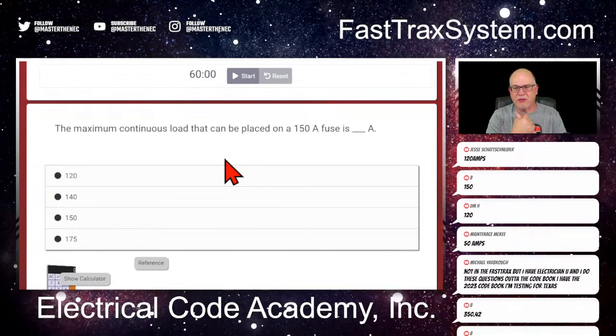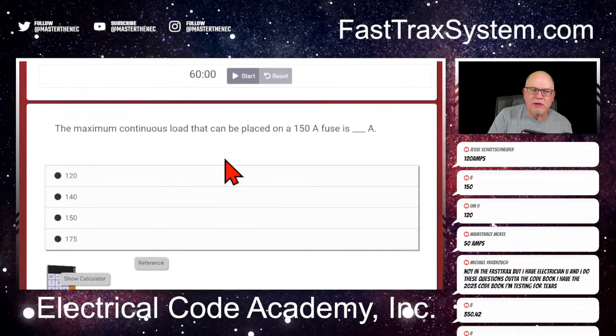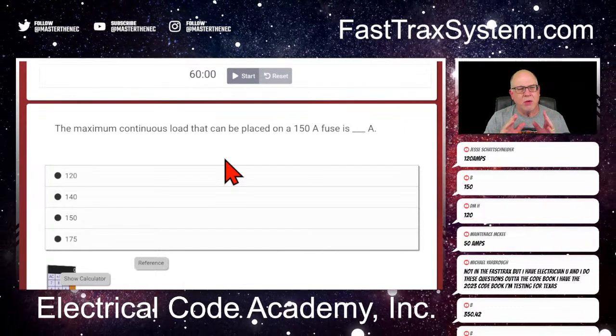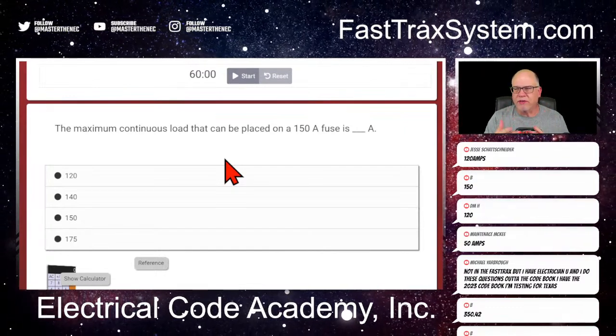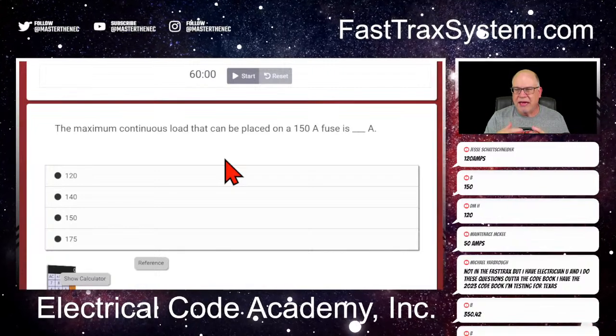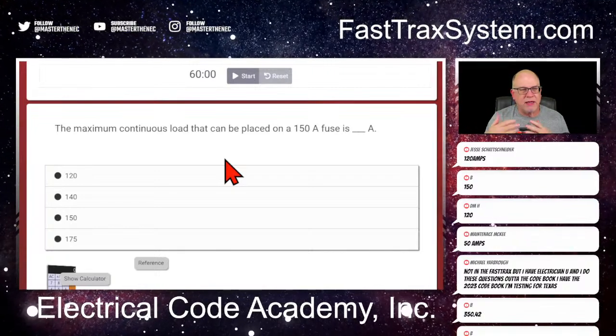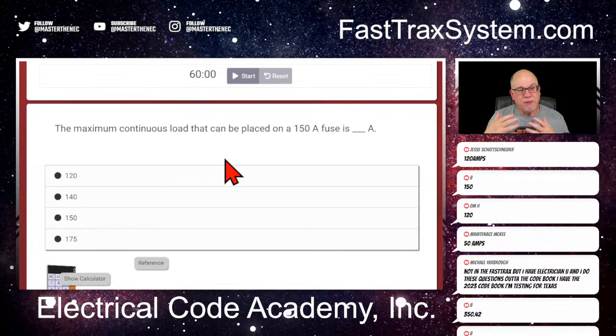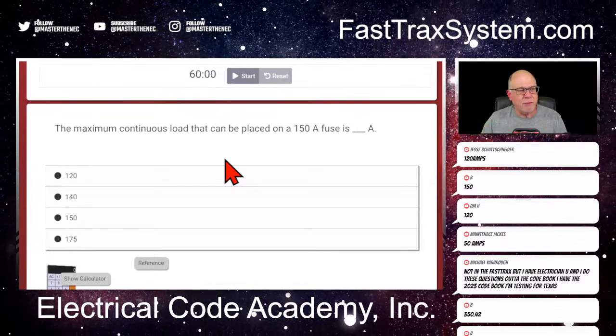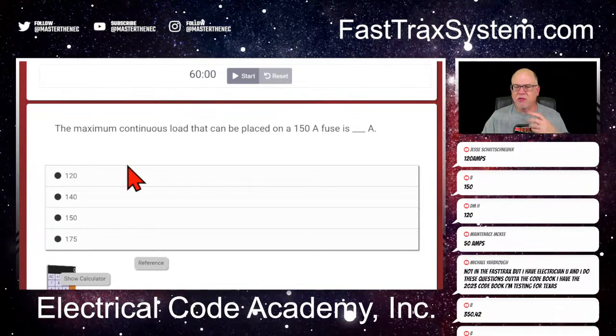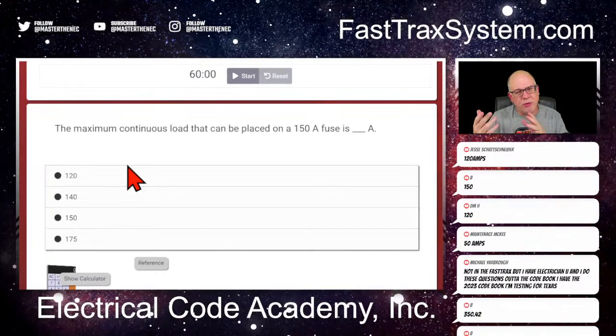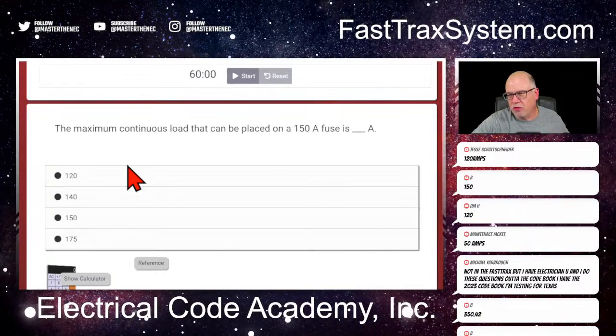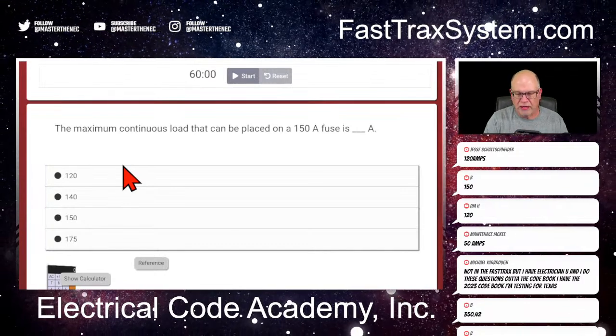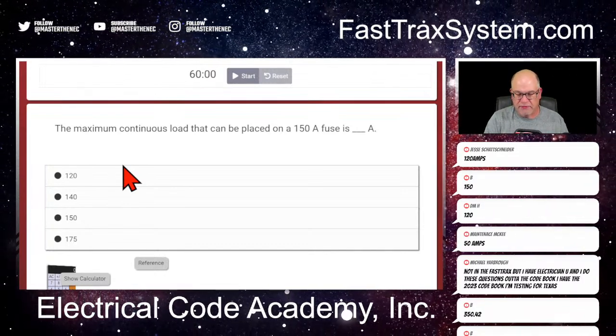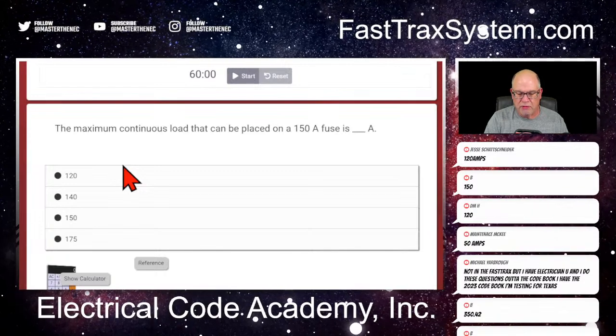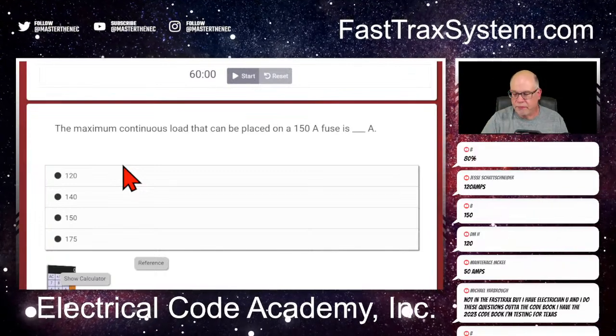So let's think about this. The maximum continuous load. Now, I've taught this to people a lot when it comes to an overcurrent device, and the maximum continuous load that can be placed on it is what? So if it was the conductor, you'd be doing it 125%, right? If it is the breaker, then you're gonna be doing it at 80%, right? So let's see what we've got here. Let's see how that works out. So if we did 150 times 0.80, it's going to be 120, right?